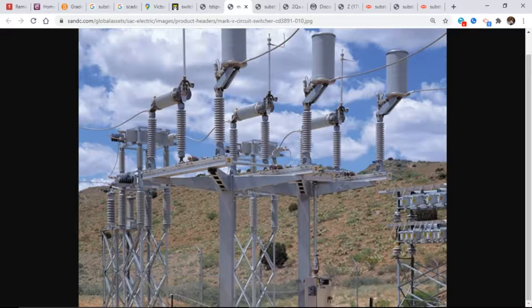So you're able to do protection, you're able to open and close switches, you're able to do monitoring for hopefully 24 hours on that battery bank. So 120, 240 does not control a substation in the sense that if I lose power to the substation, I lose all communications and control. No, it charges a battery bank, and that battery bank is going to give you hopefully 24 hours worth of monitoring and control in that station. Is that your question? Yep. All right. If you go outside of the 24 hour period, SCADA's monitoring your battery bank voltage. If that battery bank voltage starts going down, you can actually pull a generator in there, and you'll keep the generator in until you're able to get full power restored and have a generator charging those banks.